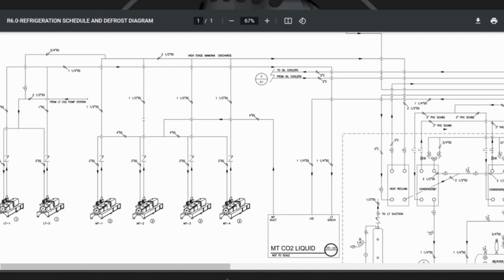Yeah, a lot of the first transcritical systems that came out, and Kevin, you can attest to this, didn't have a lot of redundancy as far as if something happened to one side of the CO2. Basically, if something happened, it's going to hit that relief pressure and blow. Is that correct, Kevin? Yeah, that's a customer issue, 100%. That's the customer not wanting to pay for a backup generator or a backup system.